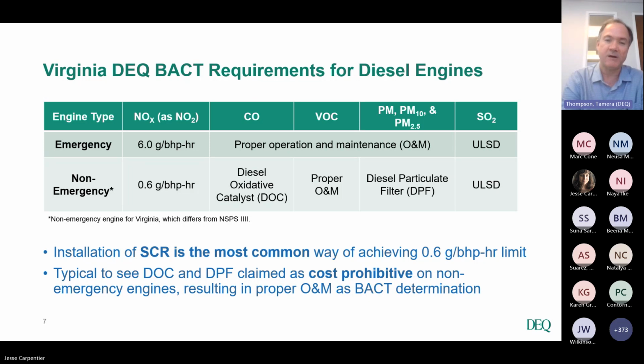SCR is the most common way of achieving that 0.6 standard. The 6.0 standard for emergency engines is applied at max capacity, as opposed to over the full load range of an engine. So we normally implement that in a permit through an hourly emission limit based upon the maximum capacity of the particular engine and horsepower.